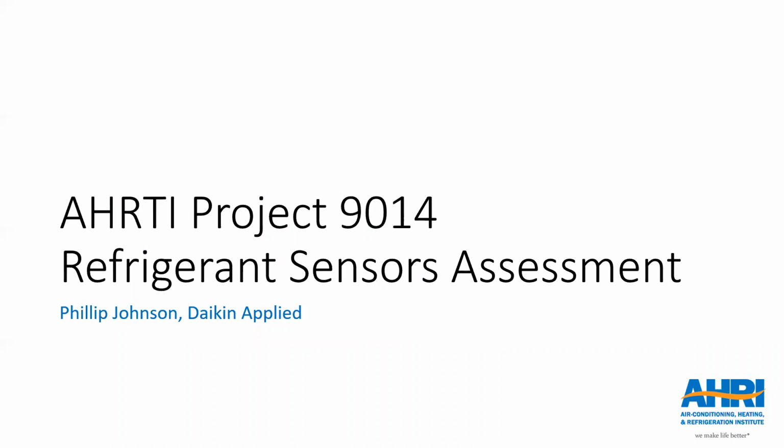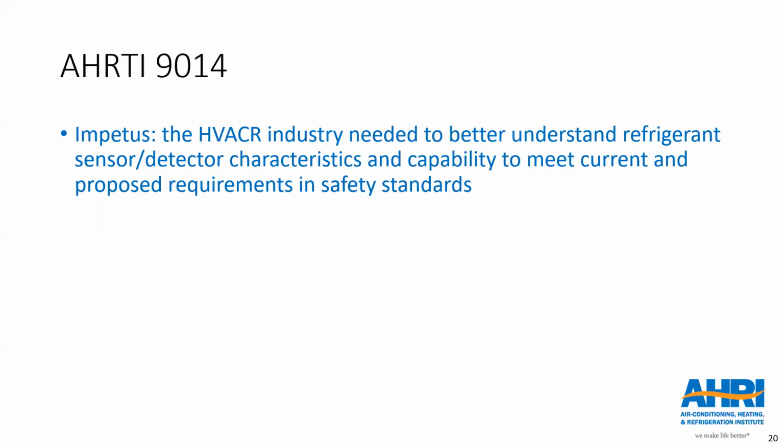So the impetus for this research project was to better understand the characteristics of refrigerant sensors and detection systems. The industry needed an in-depth assessment of the capability for commercially available devices to meet the requirements in safety standards, or the new and revised requirements that were proposed for upcoming editions of those standards, at the time the project started. Next slide, please. And next again.